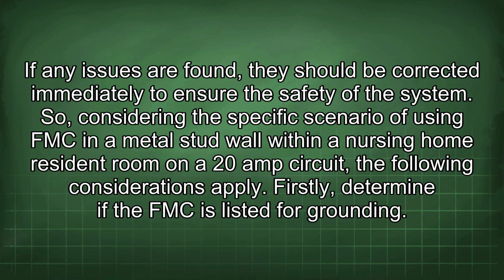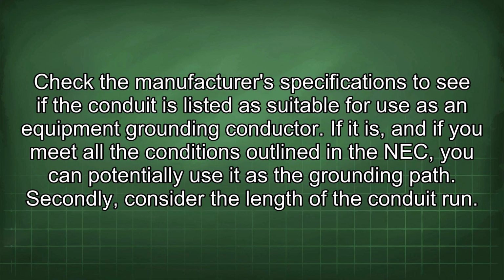So, considering the specific scenario of using FMC in a metal stud wall within a nursing home resident room on a 20 amp circuit, the following considerations apply. Firstly, determine if the FMC is listed for grounding. Check the manufacturer's specifications to see if the conduit is listed as suitable for use as an equipment grounding conductor. If it is, and if you meet all the conditions outlined in the NEC, you can potentially use it as the grounding path. Secondly, consider the length of the conduit run.